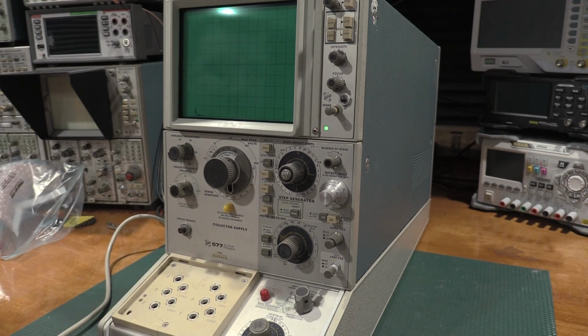So the 576 is designed for the power band, power electronic, or power silicon. 577, small signal silicon, but we still can go to exceedingly high voltages, 1600 volts, and we have much better current resolution on the 577. The 576 only goes down to 1 microamp, although it can do 1 nanoamp in looking at base currents. So from a measurement standpoint, especially in small signal, 577 actually does a little bit better job than the 576. Turn off the beam guns.